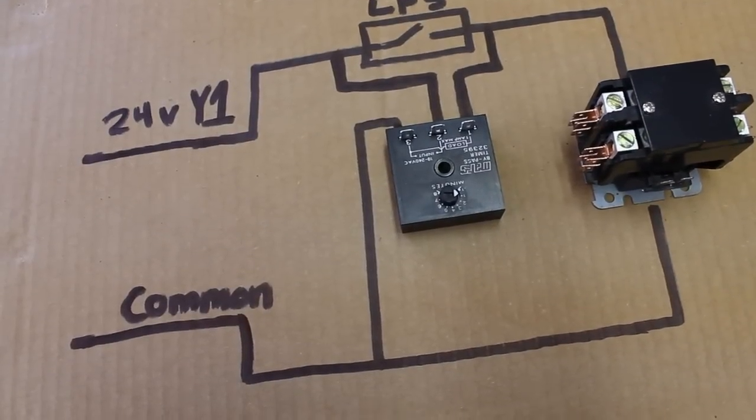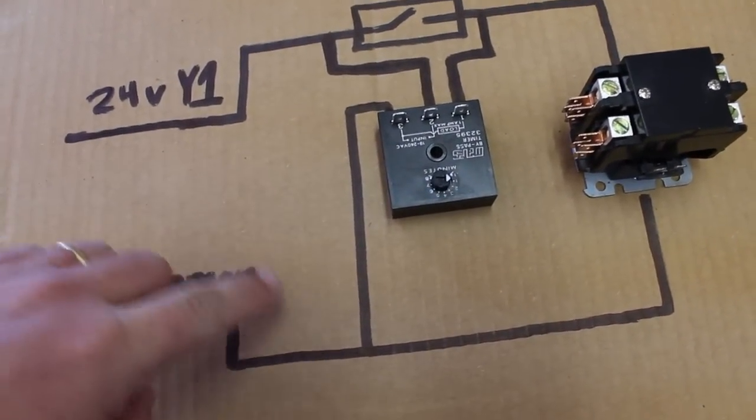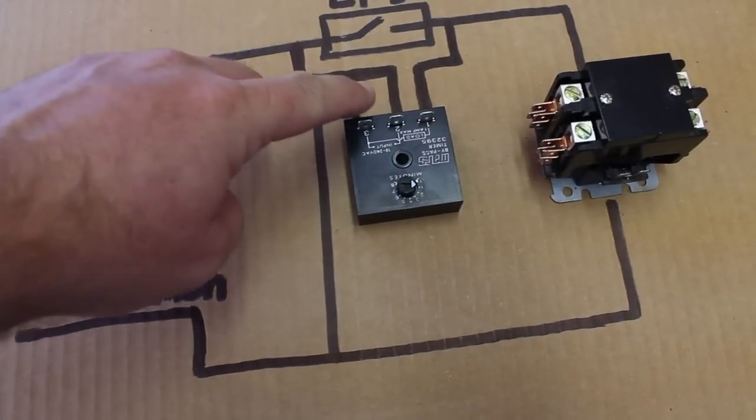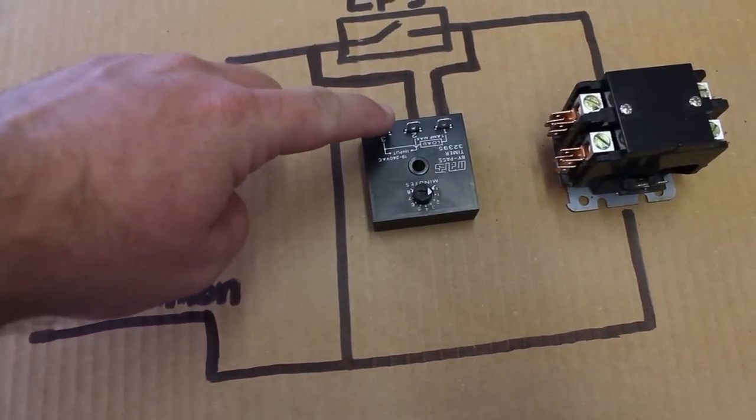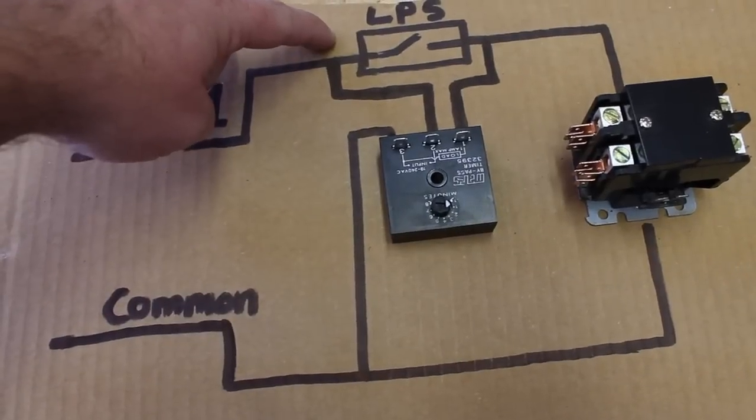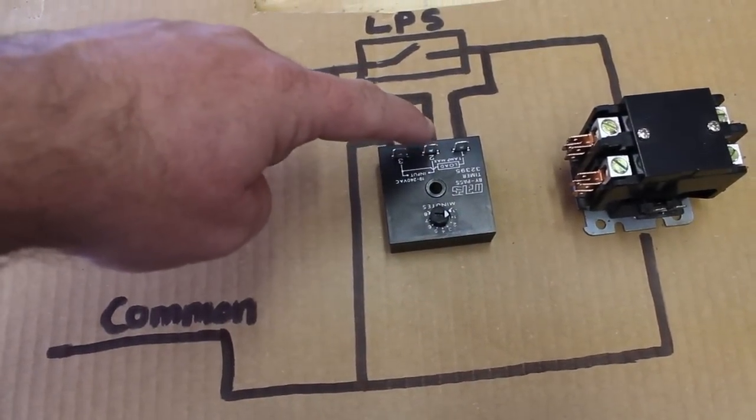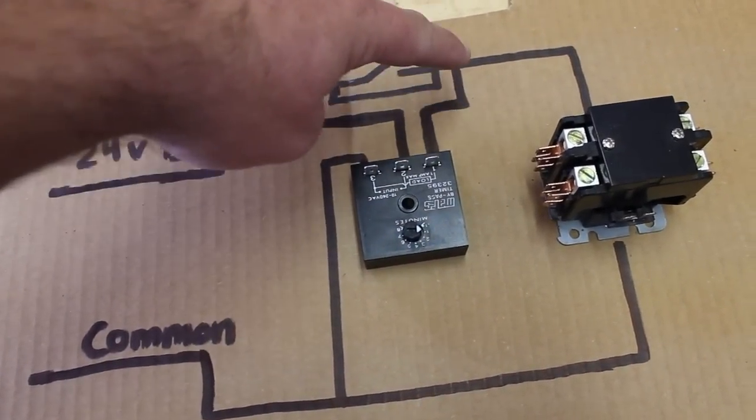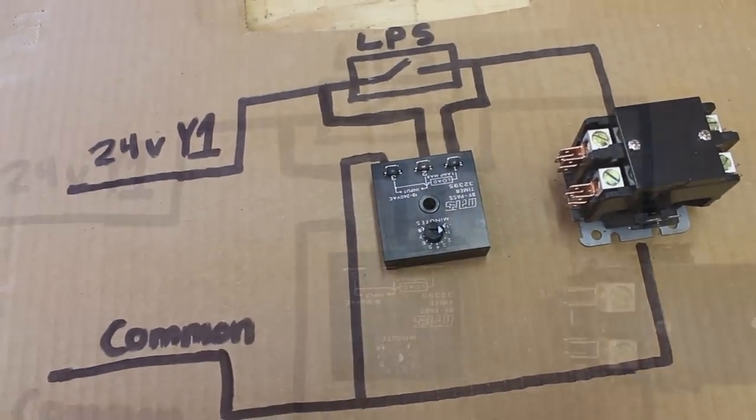As you can see, we have common coming into terminal number three on the relay. One side of Y1 before the low pressure switch comes into number two, and number one goes back to the other side. Let's take a closer look at that.